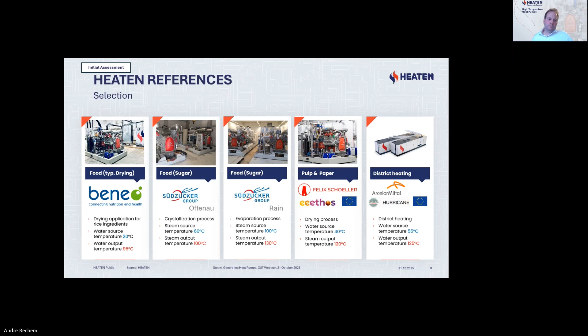Starting with Beneo, this is for us more a low temperature case. However, the customer in this specific case was interested in a very high temperature lift, wanting to preheat the drying air as much as possible. This can be done with a single stage from 20 all the way up to 95 degrees.